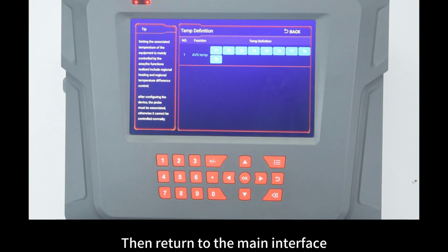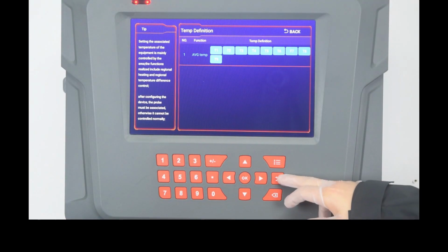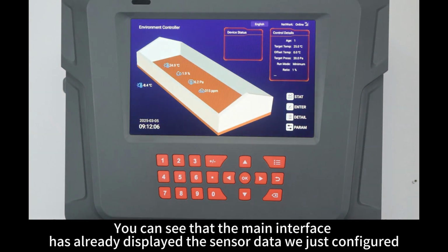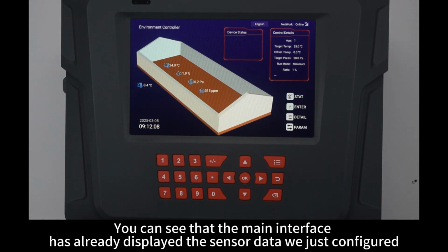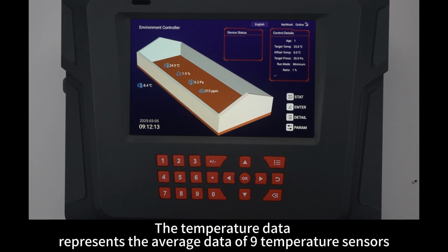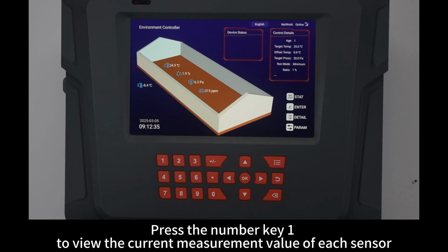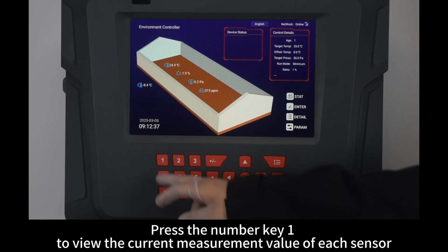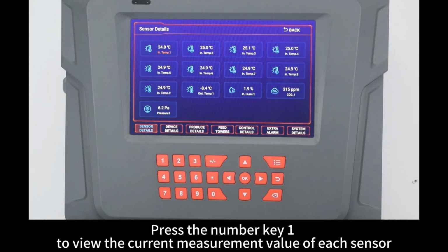Then return to the main interface. You can see that the main interface has already displayed the sensor data we just configured. The temperature data represents the average data of 9 temperature sensors. Press the number key 1 to view the current measurement value of each sensor.